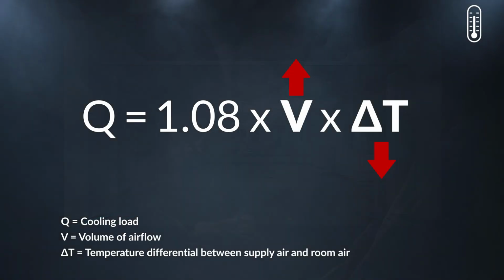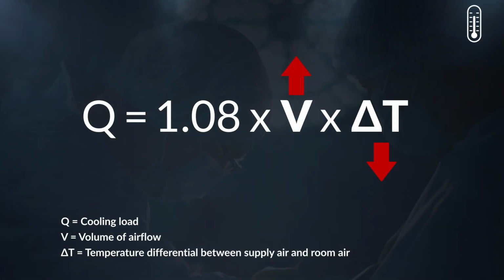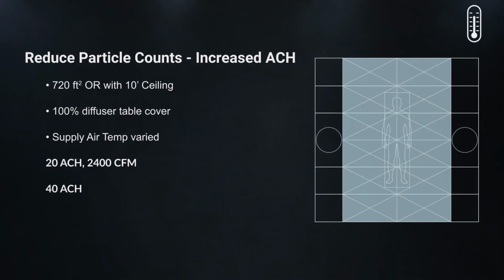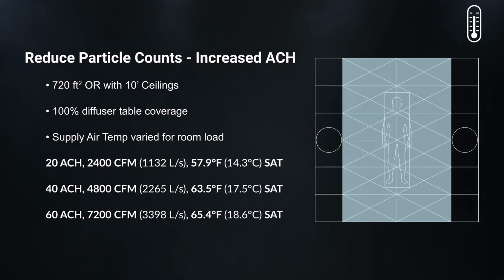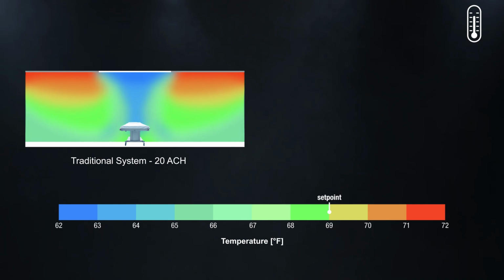The elevated air change rate allows for warmer air to be supplied to the space while still meeting cooling load requirements. At the minimum 20 air changes per hour, the supply airflow over the surgical table is quite cold and tapers significantly, leaving parts of the surgical zone underconditioned.